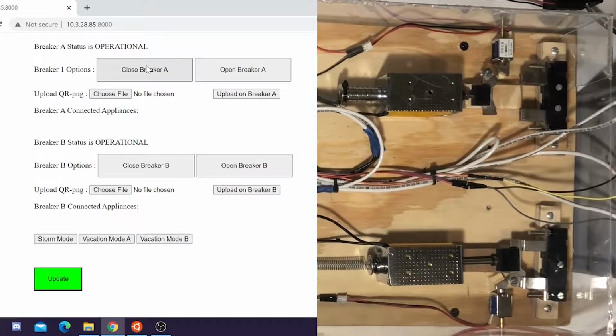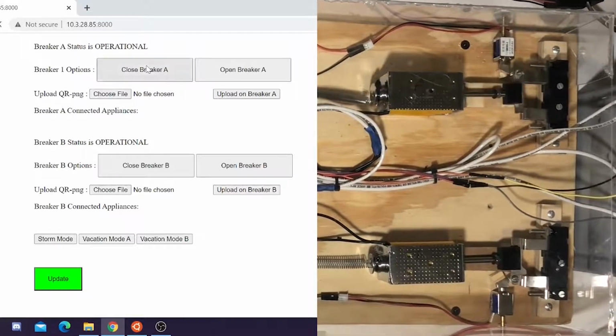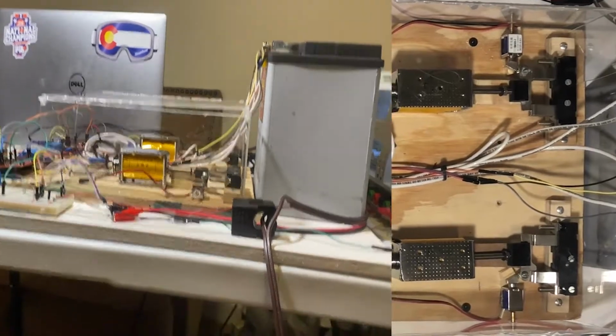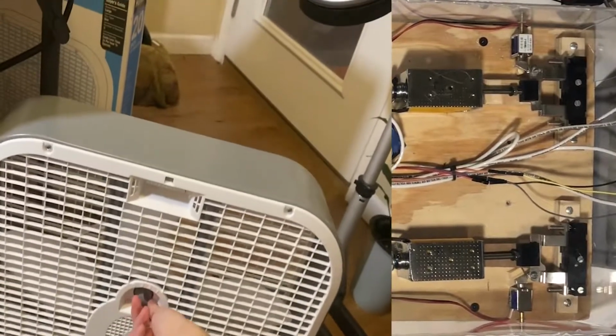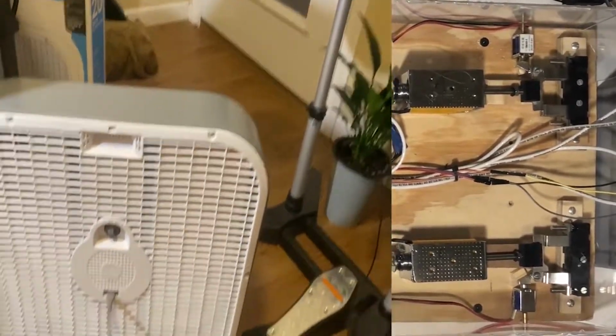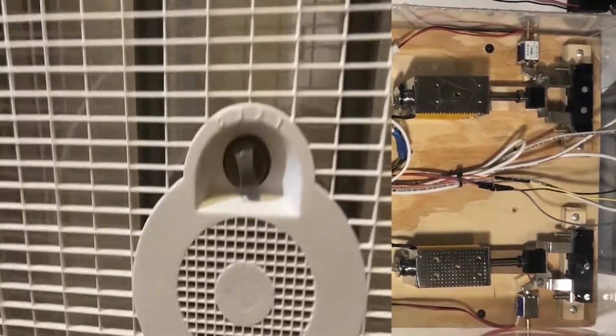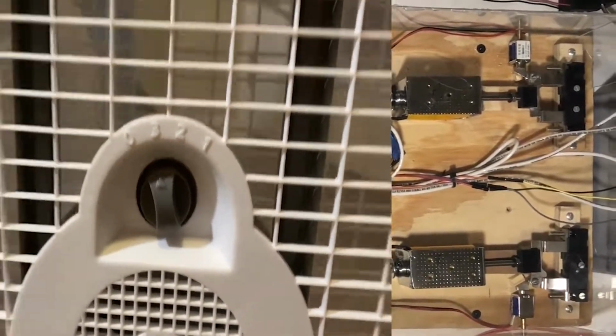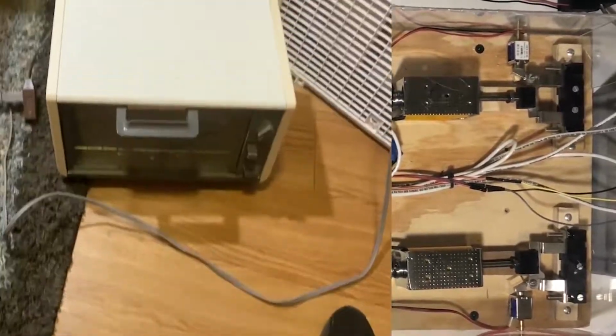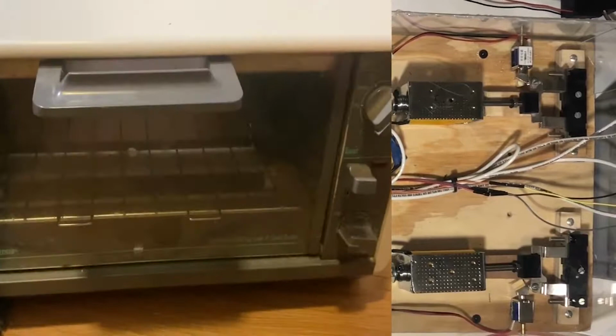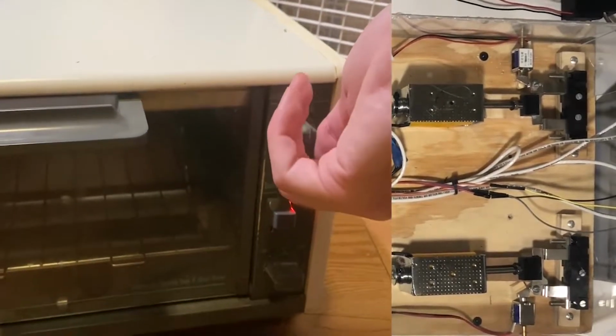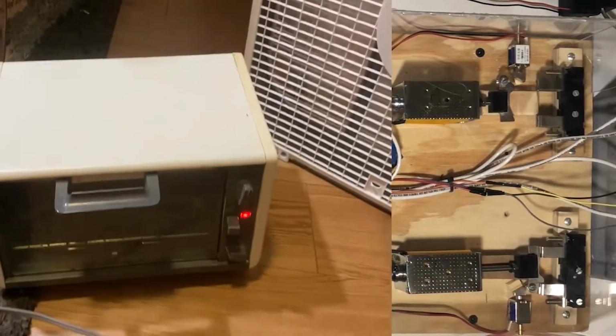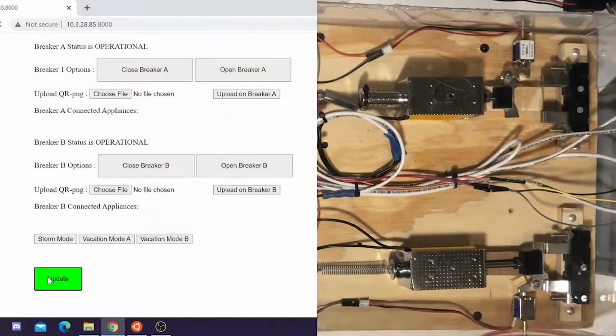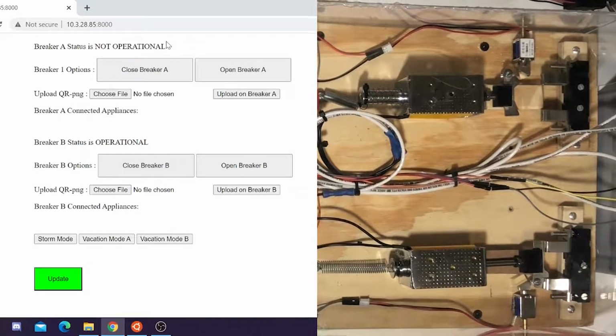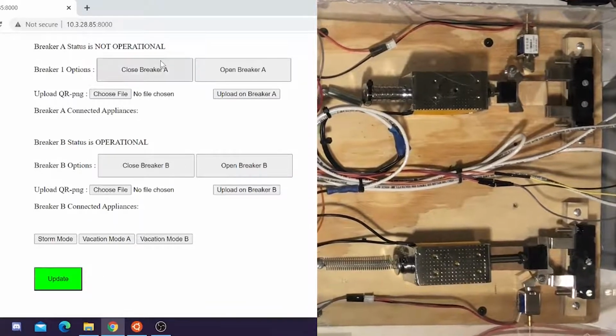Then we close again and proceed to check CT functionality. A fan is turned on, which is connected to breaker B, and we see that it stays closed, indicating that a trip has not occurred and that the breaker is operational. Next, the toaster connected to breaker A is turned on, and this will trip the breaker. This is verified here. We can now see that the breaker status for A has changed to not operational. Once we close the breaker, it goes back to operational.